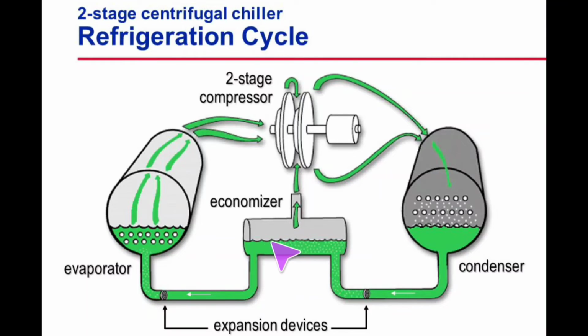Then we come over, and so now we've got this 10 degree subcooled liquid refrigerant coming through into the outlet of the economizer as a pure liquid again. Okay, so coming into the economizer, we're at that 80-20. Coming out, we're back at a full liquid state. Then we go through the final flash point, which is the second stage flash, where we then enter the evaporator.